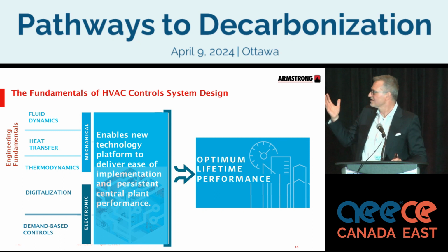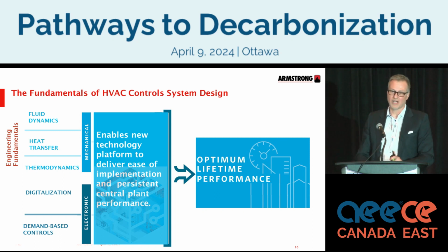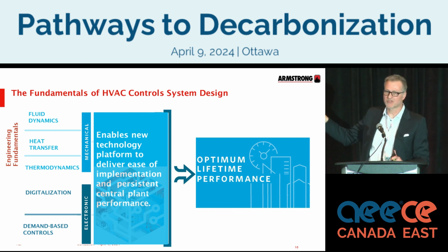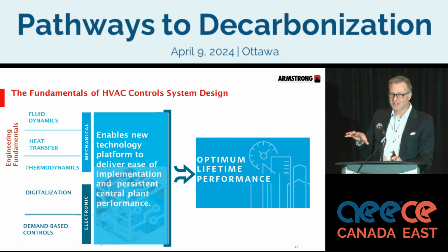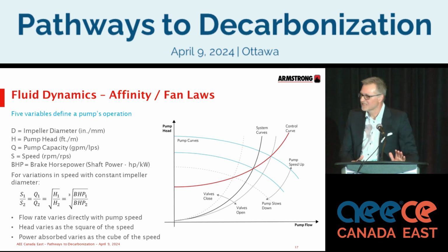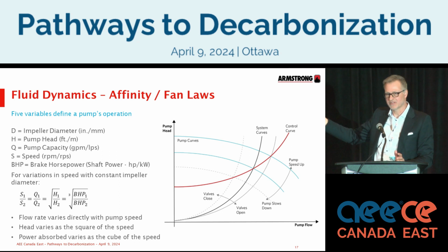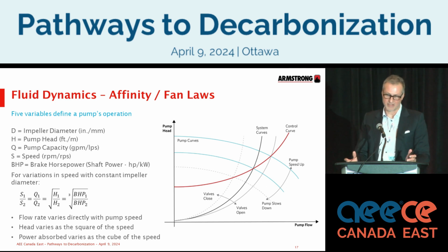And fundamentally, HVAC controls are simply based on second and third year mechanical engineering principles: fluid dynamics, heat transfer, and thermodynamics. Once you understand those principles, all we're doing is looking at digitalization and then demand-based controls. And we're going to get into more detail on what digitalization and demand-based controls are and where that pathway leads. But if we look at fluid dynamics, it's simply understanding the affinity laws or the fan laws. And we have now moved from a constant speed world to variable speed applications: variable speed drives on our chillers, on our pumps, and on our fans.